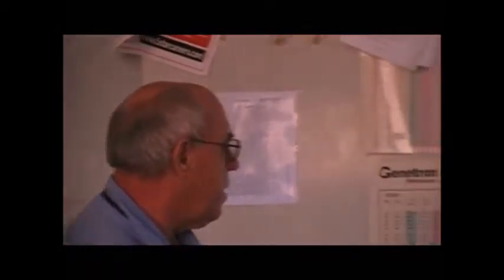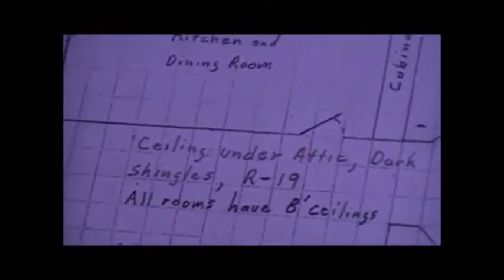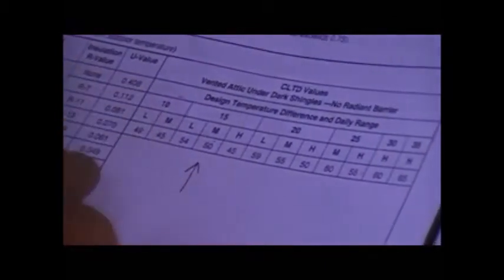All right, let's start with our ceilings since we're moving on down our spreadsheet. In our particular example, our ceilings are going to fall up under an attic with dark shingles. We're going to have R19 insulation. So we go to our J manual once again, and we find what fits that, under table 4, 16B with R19, that is a 16B-19 if you're looking for the code, and our U value is going to be 0.049. So let me go ahead and identify our ceilings.